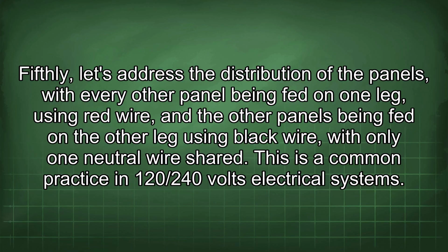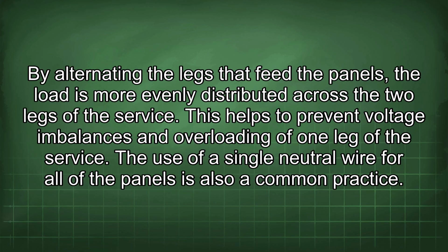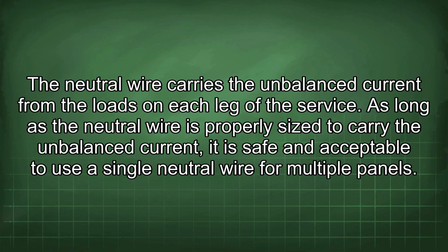120/240 volt electrical systems. By alternating the legs that feed the panels, the load is more evenly distributed across the 2 legs of the service. This helps to prevent voltage imbalances and overloading of one leg of the service. The use of a single neutral wire for all of the panels is also a common practice. The neutral wire carries the unbalanced current from the loads on each leg of the service. As long as the neutral wire is properly sized to carry the unbalanced current, it is safe and acceptable to use a single neutral wire for multiple panels.